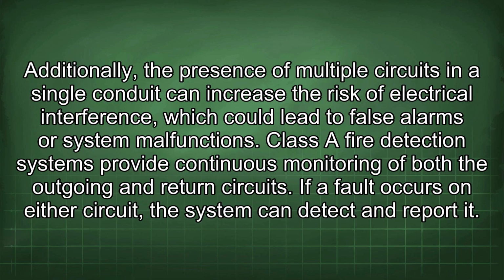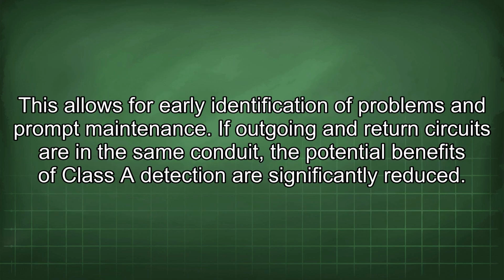Additionally, the presence of multiple circuits in a single conduit can increase the risk of electrical interference, which could lead to false alarms or system malfunctions. Class A fire detection systems provide continuous monitoring of both the outgoing and return circuits. If a fault occurs on either circuit, the system can detect and report it. This allows for early identification of problems and prompt maintenance. If outgoing and return circuits are in the same conduit, the potential benefits of Class A detection are significantly reduced.